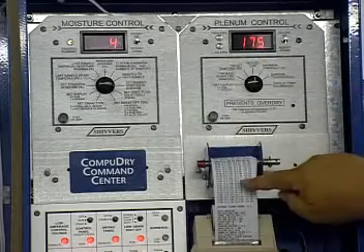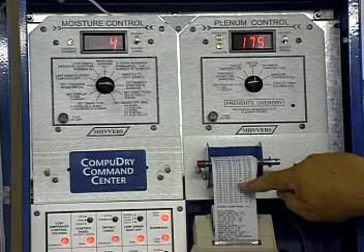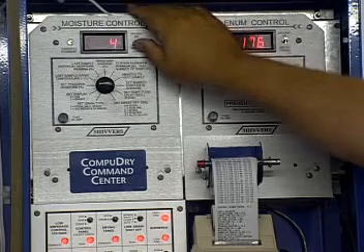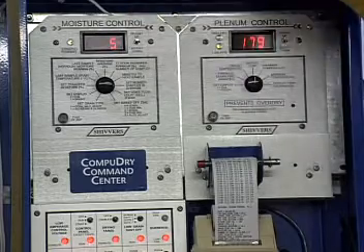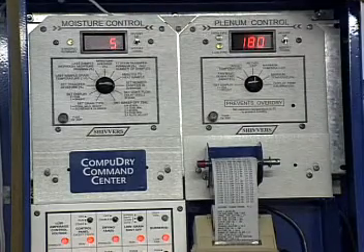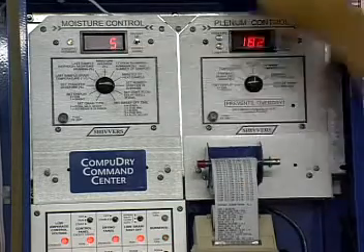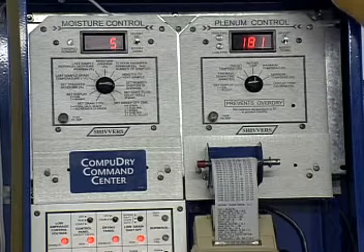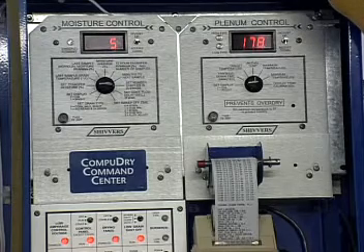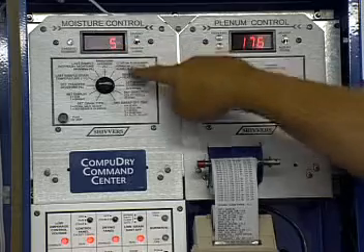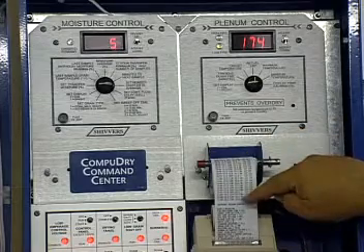Remember, every time it gets one of those offs, it starts that average over again: average 1, 2, 3, and 4. It starts those over again. So what I would do is probably set this up to number 5. Because if it had been set at 5 before, it would have stayed running longer, because the one that it turned off was almost there but not quite there. So I'd set it up to 5. And in a period of a day's time, you may get 200 more bushels through this system, not 200 bushels an hour, but 200 bushels more by just turning from 4 to 5. Don't do it automatically. Learn how to read and evaluate your tape, and that's the importance of having this printer.